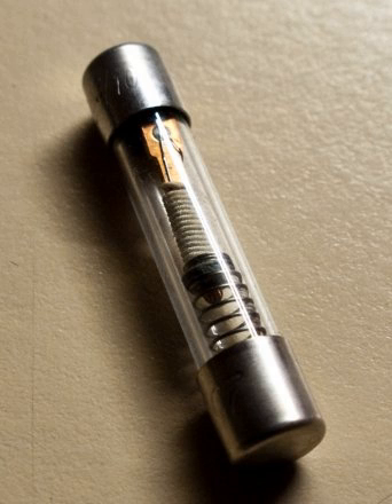This is a North American tri-national standard: ANSI/UL 4248-11, CAN/CSA C22.2 No. 4248.11-07 (R2012), and NMX-J-009/4248/11-ANCE. Existing Edison fuse boards can easily be converted to only accept rejection base type S fuses, by screwing in a tamper-proof adapter. This adapter screws into the existing Edison fuse holder, and has a smaller diameter threaded hole to accept the designated type S rated fuse.